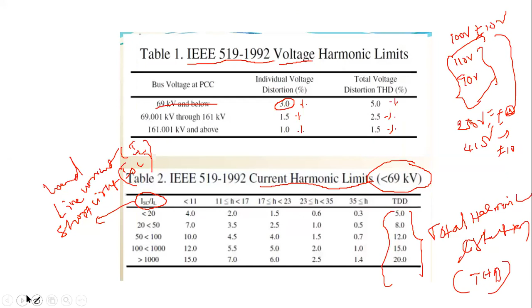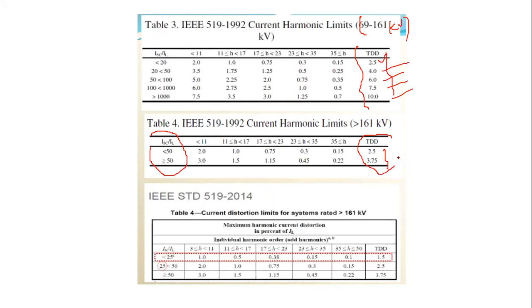Okay, now see some more standards. This is the table where we can assume the transmission voltage level is less than 69 kV. Now see this table, we can assume it as 69 to 161 kV. You can see these levels of currents. See this total harmonic distortion. How much percentage of total harmonic distortion? You will get in this system 2.5%, 4%, 6, 7, and 10%. If above 161 kV, what will happen? The total harmonic distortion percentage is 2.5 and this is 3.7. Remember, this total harmonic distortion is mainly based on the current drawn by the load.